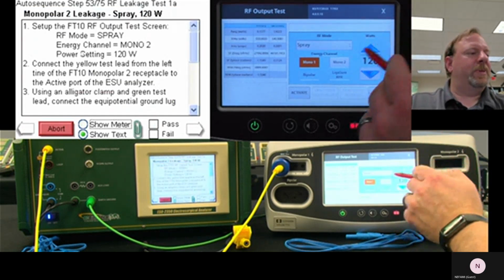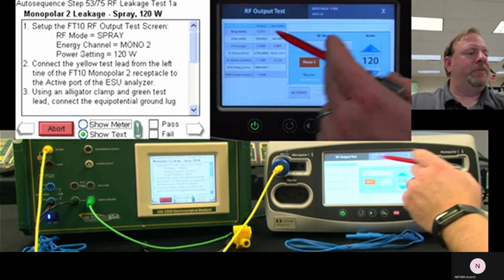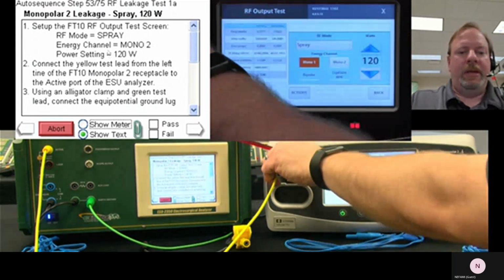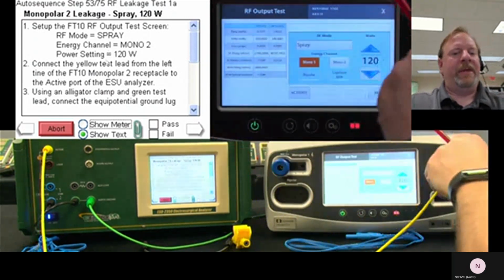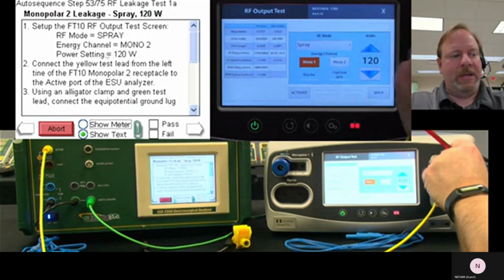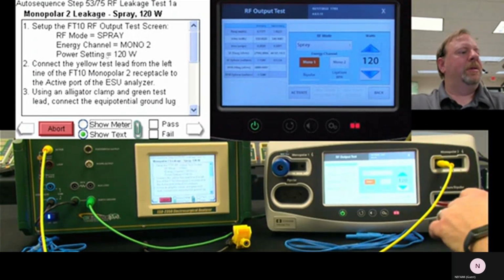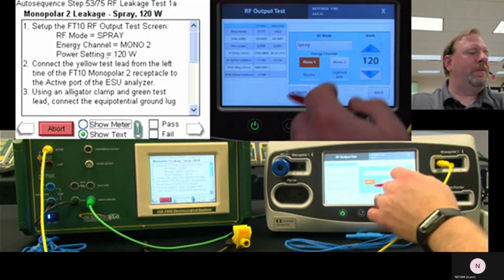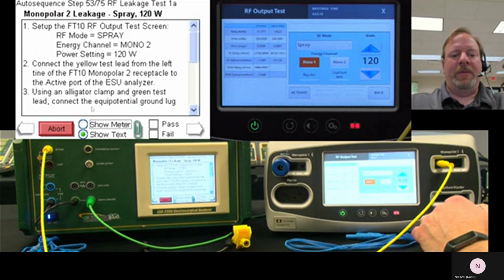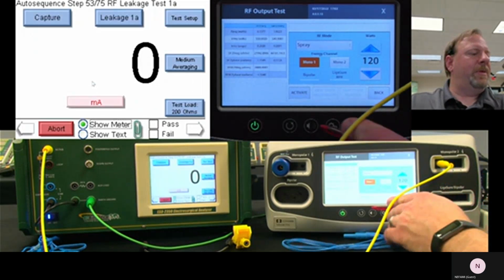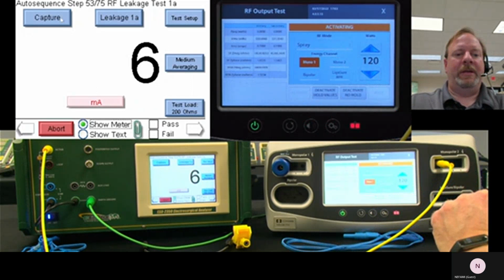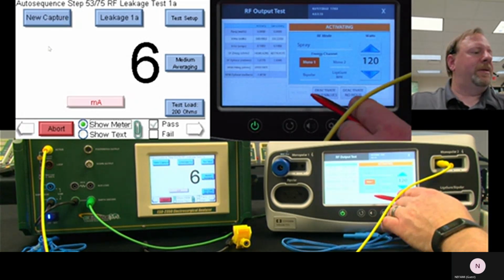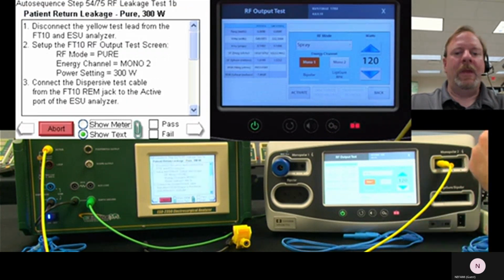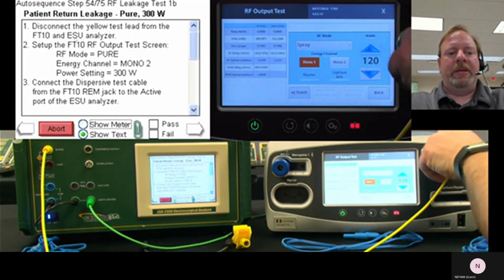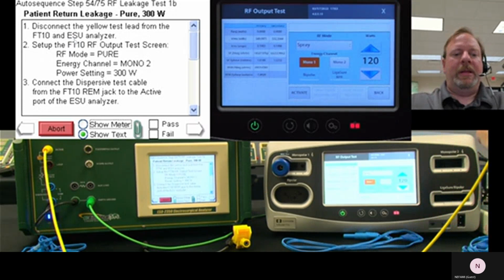So then we go to spray, monopolar 2. And connect the test lead from left side of monopolar 2. Now we're going to check that leakage. Worst case scenario, spray, maximum power. They've already determined what the worst case scenario is, so all we have to do is follow their lead. That is in the service manual and the auto sequence. Disconnect the yellow lead, the analyzer.